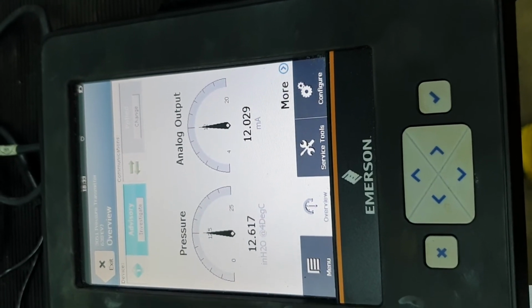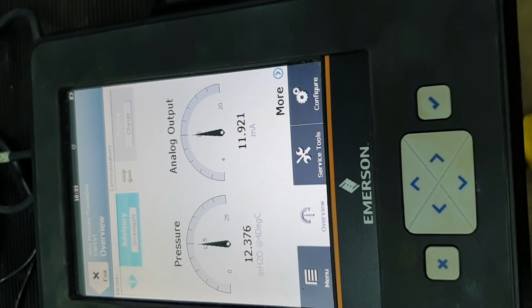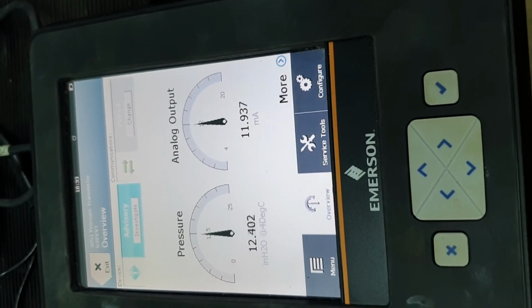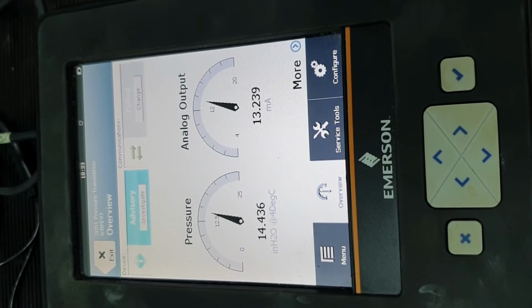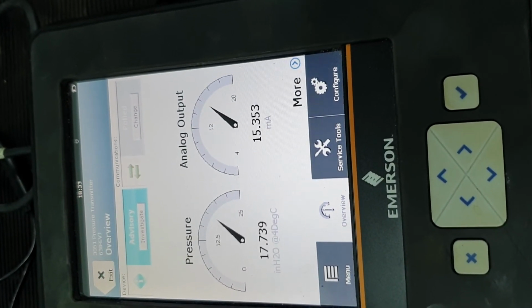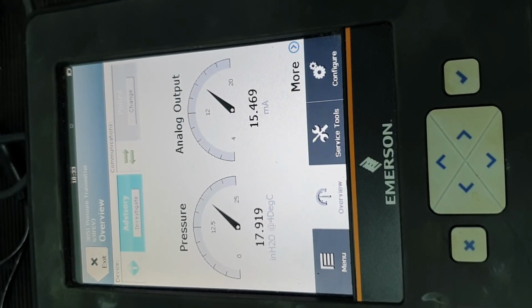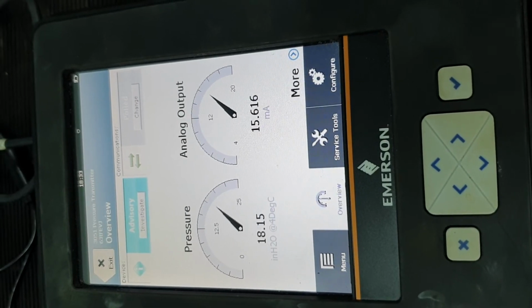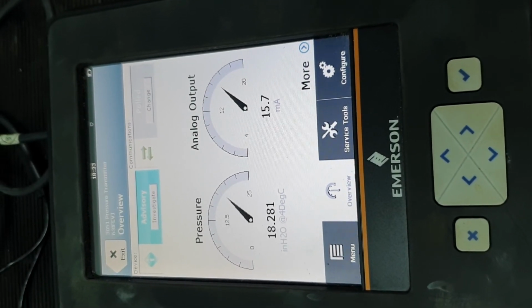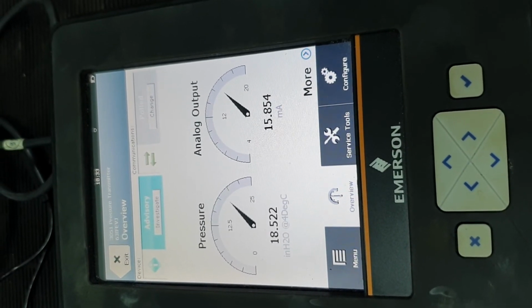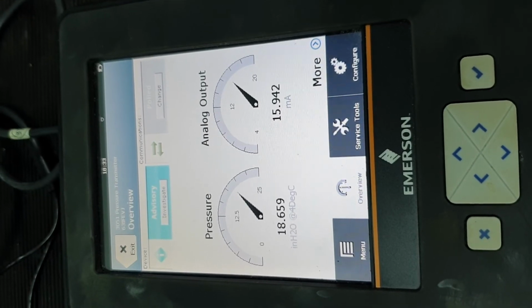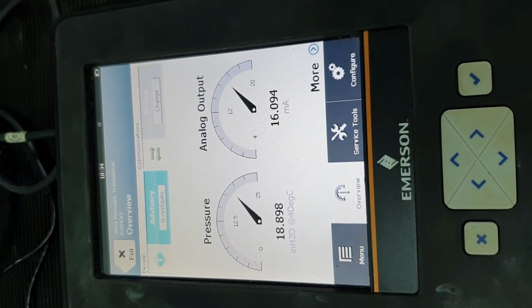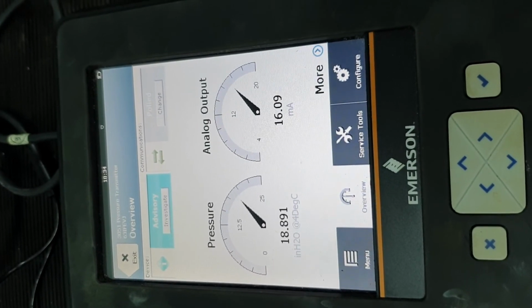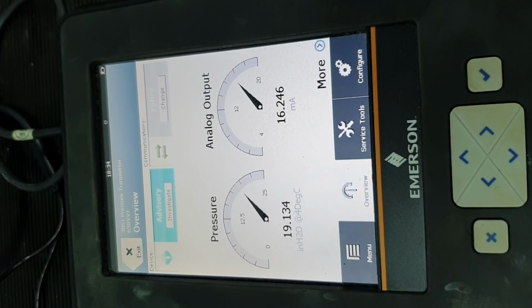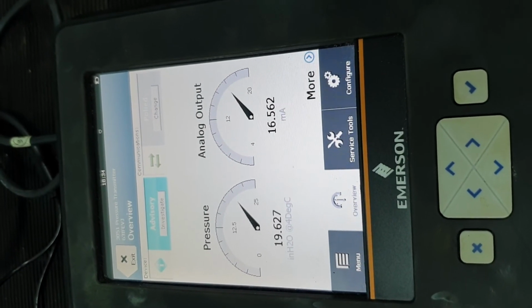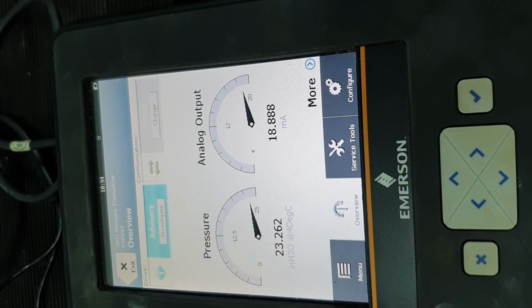Okay, next we will go into the 75%, which is equivalent to 18.75 inches H2O. This one we should theoretically be getting 16 milliamp. Finally, we will go into 100%, which is about 100% pressure applied to the transmitter, which should be equivalent to 25 inches H2O. This will be equivalent to 20 milliamp.